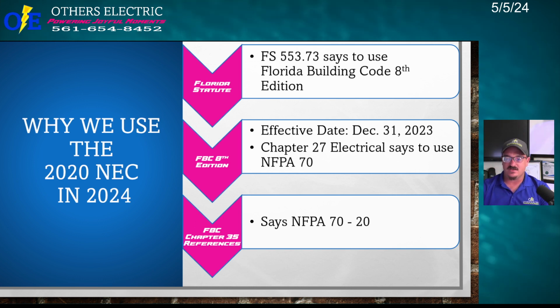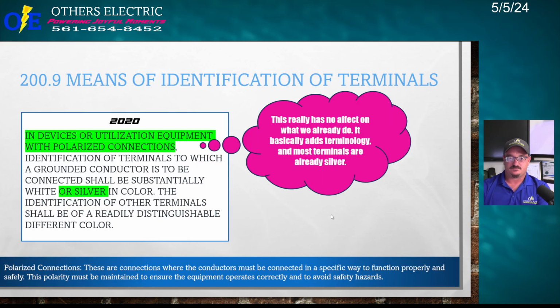And if you go to Chapter 27 in the Florida Building Code, it's the electrical chapter, and it says to use NFPA 70, okay, but it doesn't say which version of the NEC to use. 2017, 2014, 2020, 2023. So you have to go to Chapter 35 of the Florida Building Code, and it says NFPA 70-20, which is why we use the 2020 NEC.